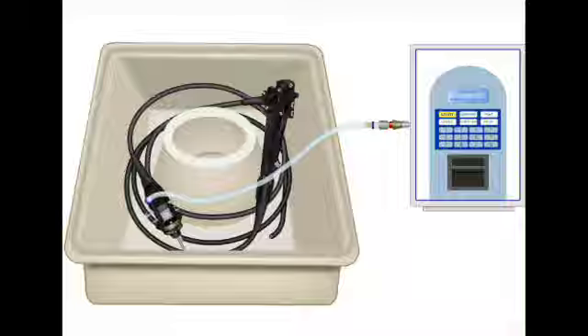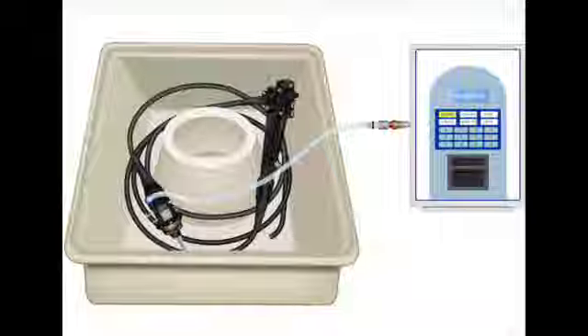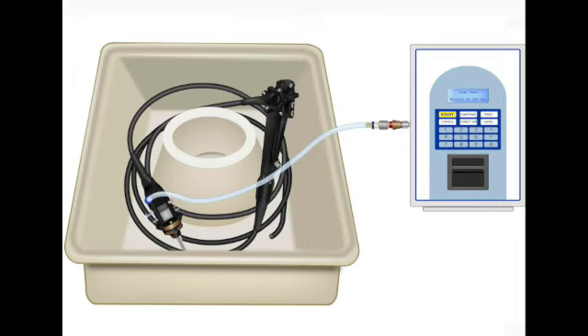Absolutely. So today, our mission is a deep dive into that exact step. The protocols for endoscope leak testing. We've gone through sources on aseptic technique, and this is really the foundation. It really is. I mean, the stakes are not theoretical at all. This is the moment, exactly. We're checking the actual mechanical integrity of the system. Exactly. And if you skip it or even just rush through it, water will get inside during the cleaning that follows. It's a guarantee. And that water causes, well, what does that cause?